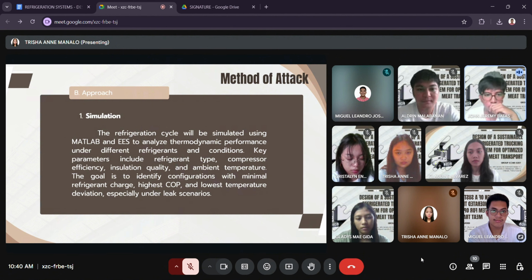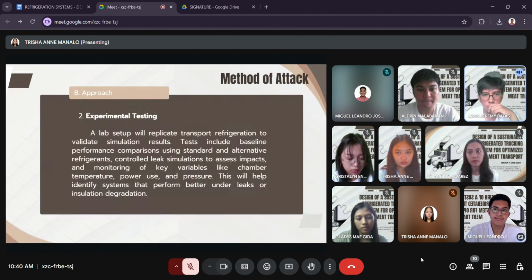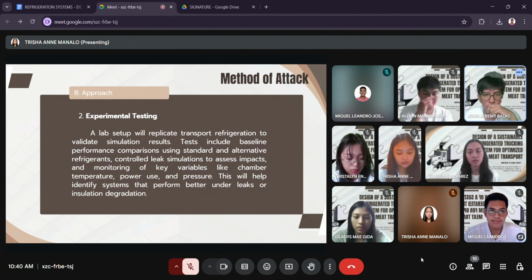Next, to support our simulations, we conducted experimental testing through a laboratory setup that simulates actual transport conditions. This includes baseline performance tests with standard and alternative refrigerants, as well as controlled leak simulations to monitor how the system reacts to refrigerant loss. We monitored key parameters like internal chamber temperature, power consumption, and refrigerant pressure to validate the simulation data.